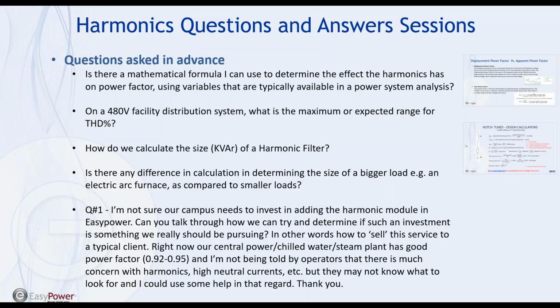Within the facility itself, there are no harmonic current distortion limits, right? You're inside the facility, you're not at the point of common coupling. So within the facility itself, there are no distortion limits. So there you're looking for best practice, and applying 519 is a reasonable practice to follow. If you exceed 519, will you have a problem? No. And now the same goes for voltage distortion.